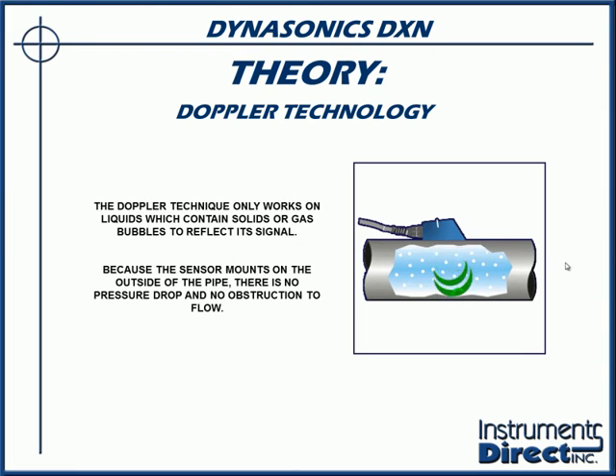Moving on to the ultrasonic Doppler technology, which is completely different. Doppler flow meters are designed specifically for applications with suspended particles in the process stream, very much like a police radar gun. They zap your car as it comes by, it gives a reflection back, and it measures how fast your car is going. Well, if there's no car, there's no reflection back. Using an ultrasonic Doppler flow meter, if there's no suspended particulate matter in the process stream, then there's no reflection back. Most ultrasonic Doppler flow meters, depending upon the manufacturer, need about 100 parts per million and anywhere from 30 to 75 microns in size. You need a reflection from that to get the signal back.